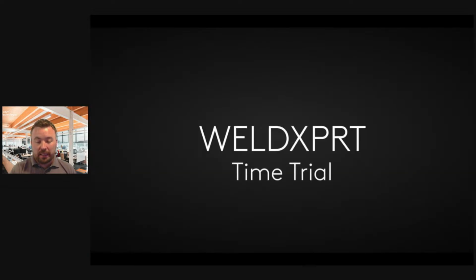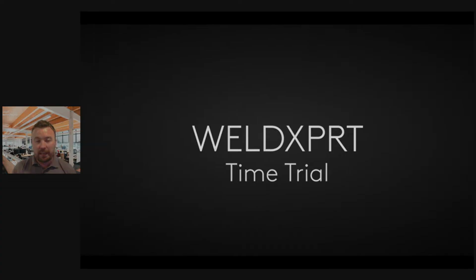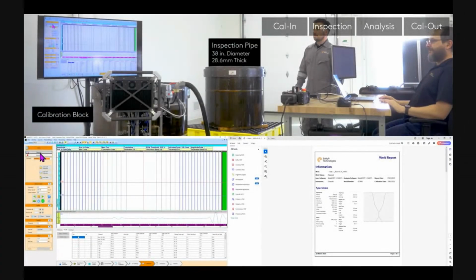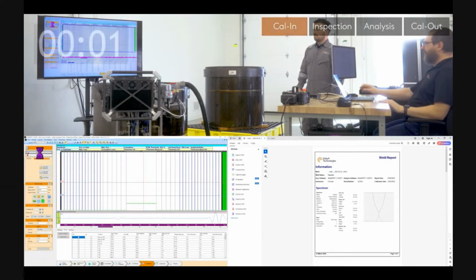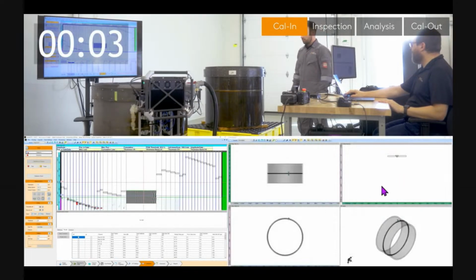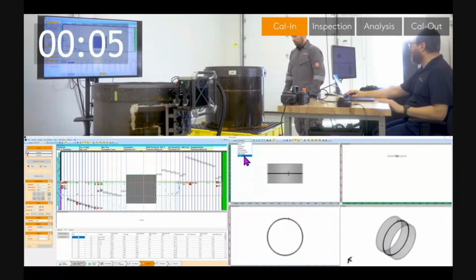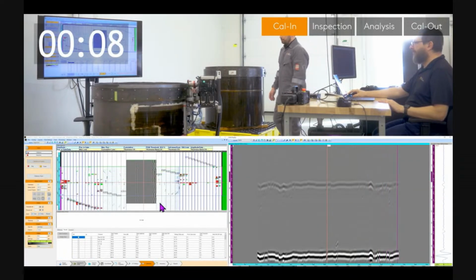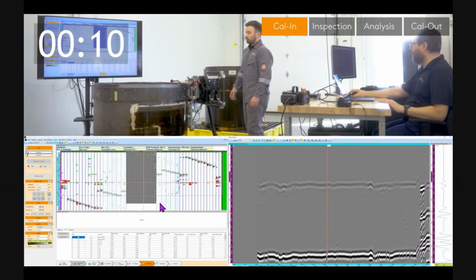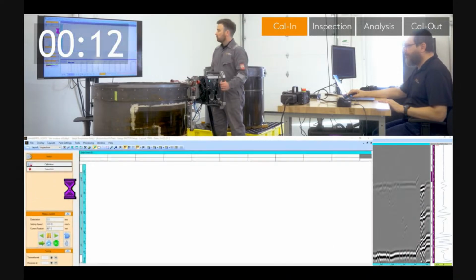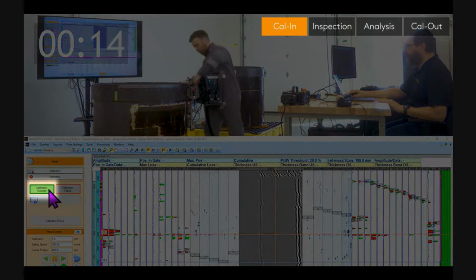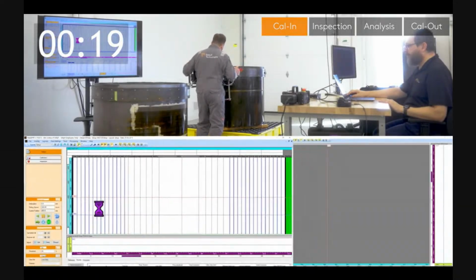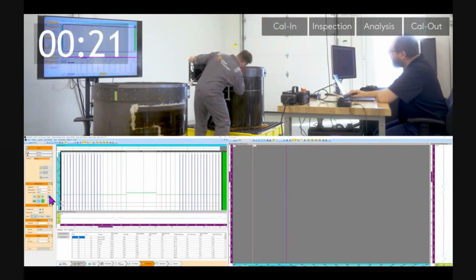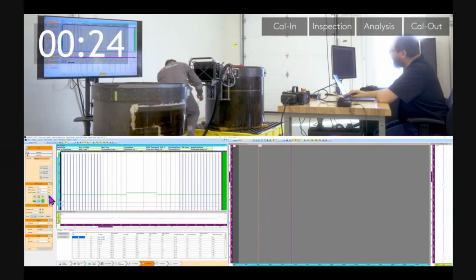So I want to show a time trial, a speed trial of this that we carried out in our lab with myself and my colleague. We're doing an inspection here of a 38-inch pipe with a 28.6 millimeter thick weld. We're first running the calibration check. We're running a calibration sequence. You may see those gray boxes in the strip chart, and they are looking for the reflectors in the calibration block. It knows they are there. All of them are in the right position with the right sensitivity and time of flight. So we get a green calibration success icon, and that calibration file is stored.